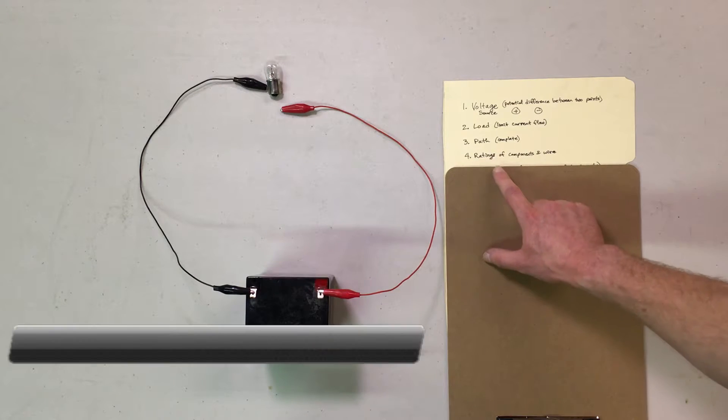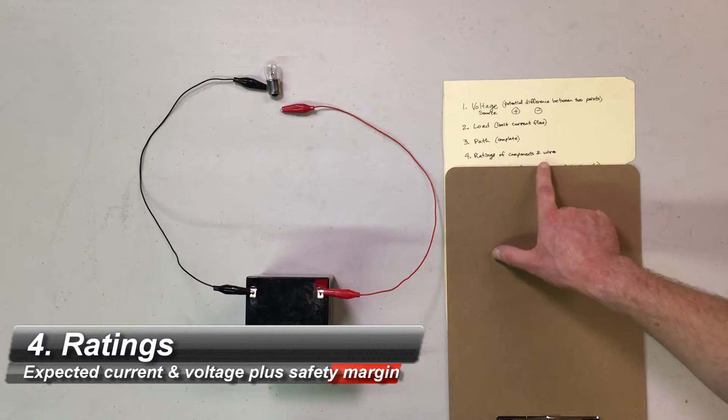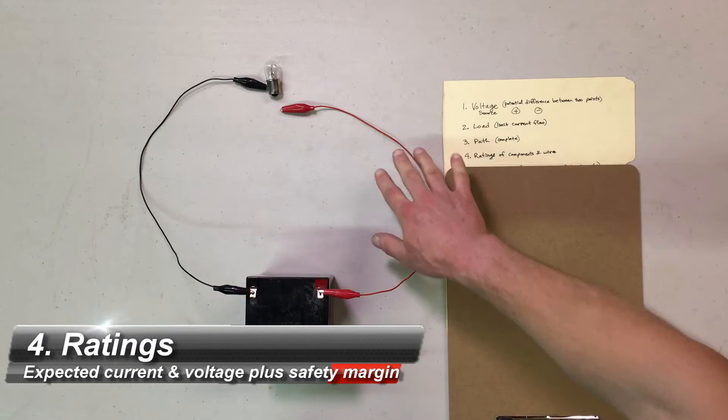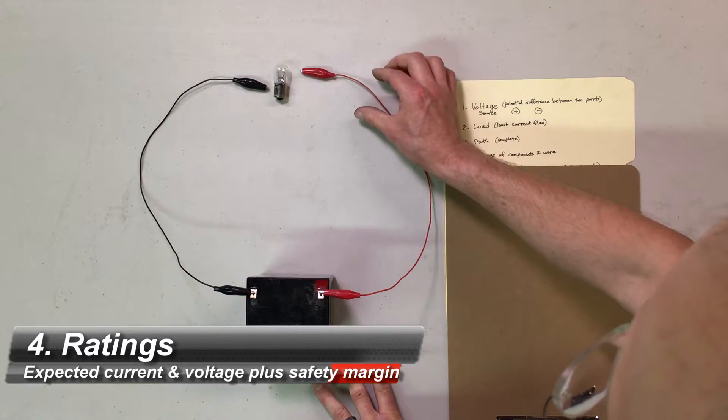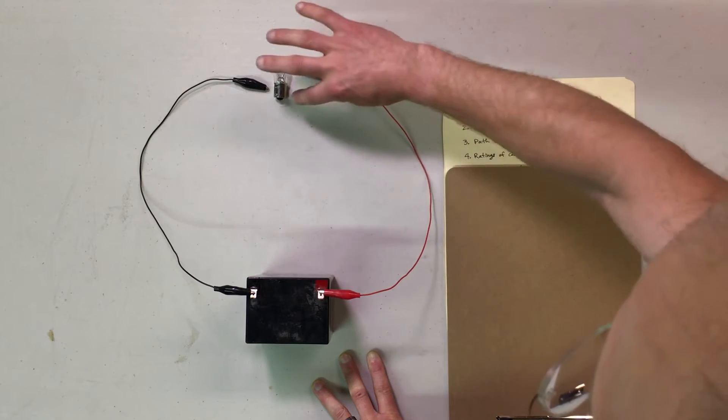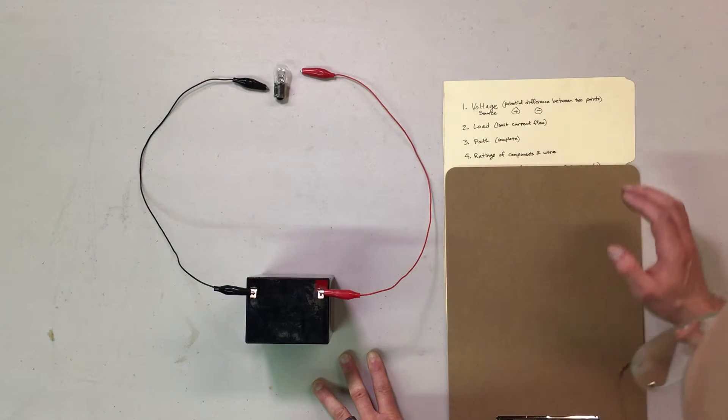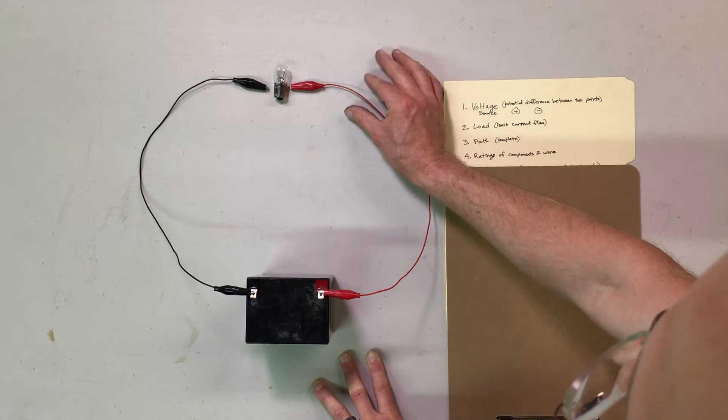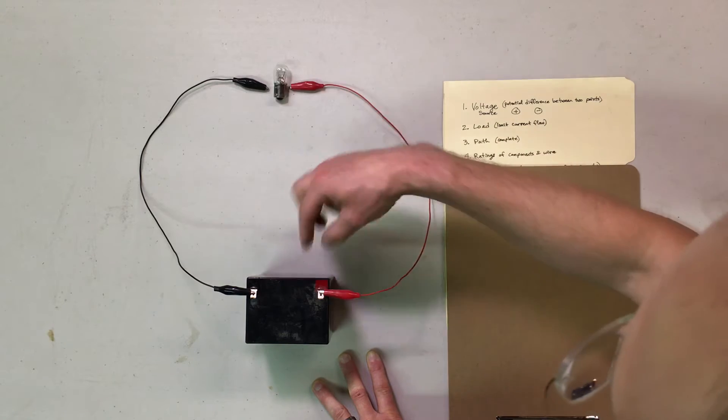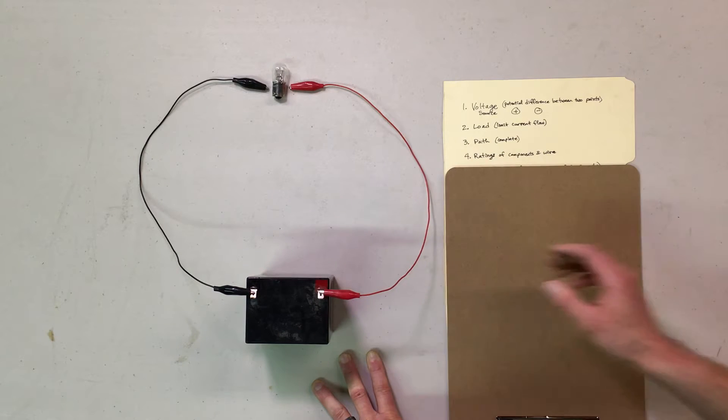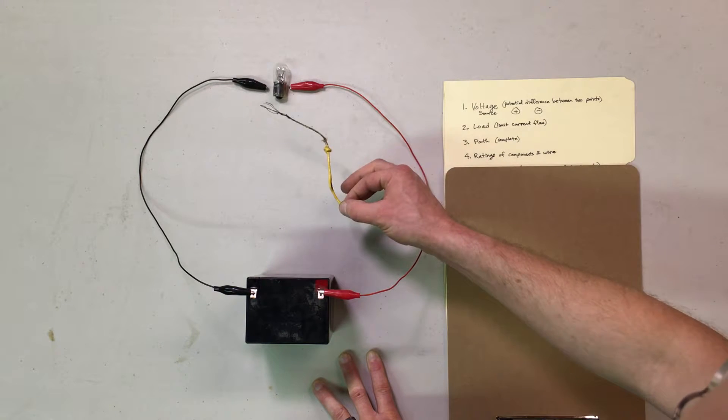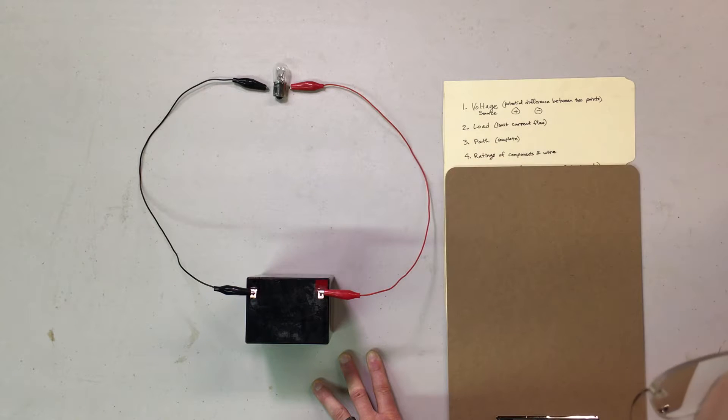The fourth thing you need is to match the ratings of your components and your wire. The wire needs to be sized appropriately so it's thick enough for the amount of flow, current flow that you're going to have running through the circuit. In other words, if the wire is too small for the current that you're flowing based on the load you have and the voltage source that you're providing, you will end up frying the wire because it will not be able to carry that much current.